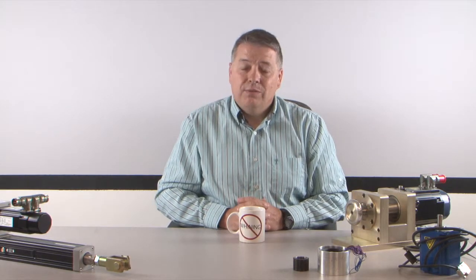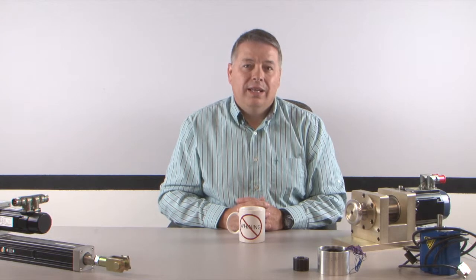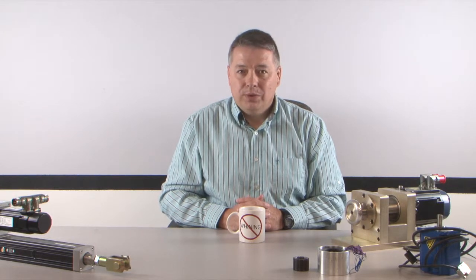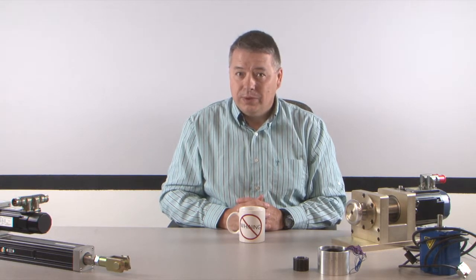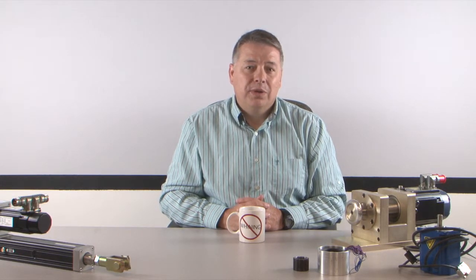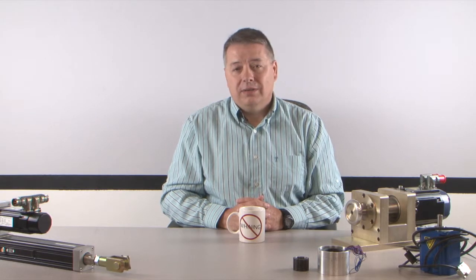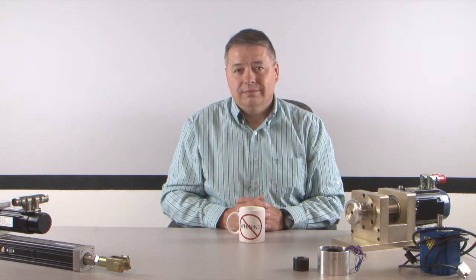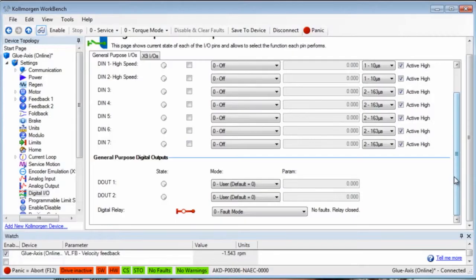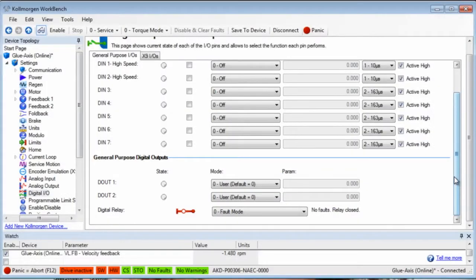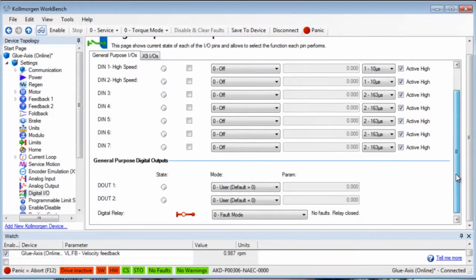To interface with the outside world, the AKD has digital inputs and digital outputs, and depending on how we set them up, we can change the function of the drive. The standard AKD has seven programmable inputs and two programmable outputs. There are also dedicated inputs for enable and a dedicated relay output for faults.